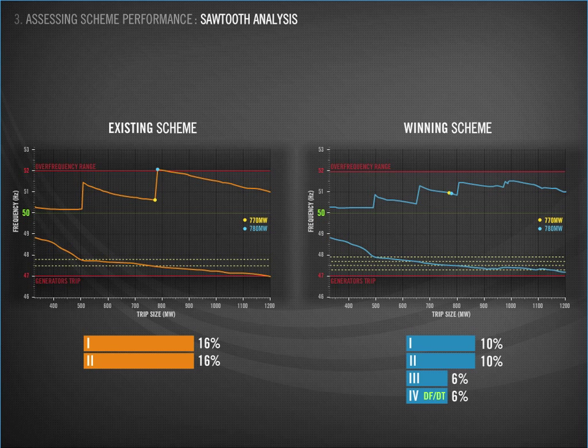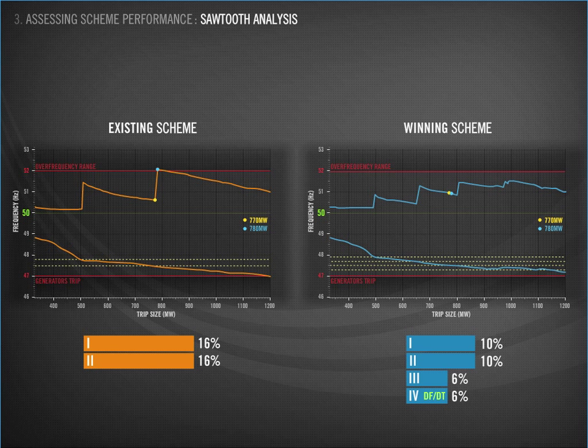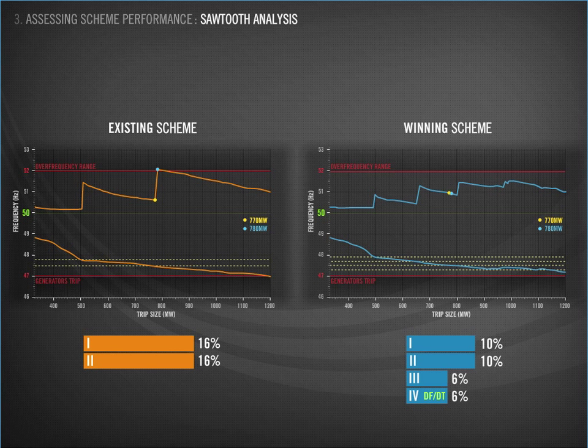On the left we have the existing scheme with two blocks of 16%. You can see on the sawtooth that there are two points where the frequency goes outside the acceptable range. On the right is the winning scheme with four blocks: 10, 10, 6, and 6%. Importantly, on the sawtooth you can see the results stay within the acceptable range. This comparison highlights what we have gained through changing the scheme. As you can imagine, there are many complex factors that contributed to this scheme design being chosen, and we will look at these next.